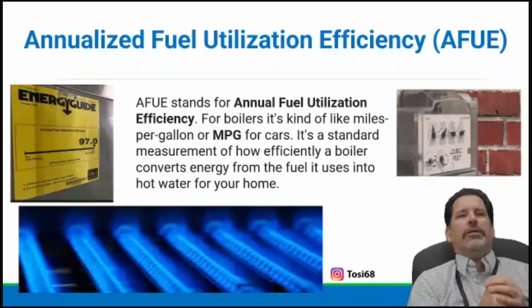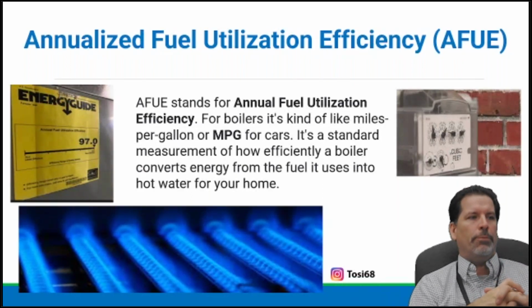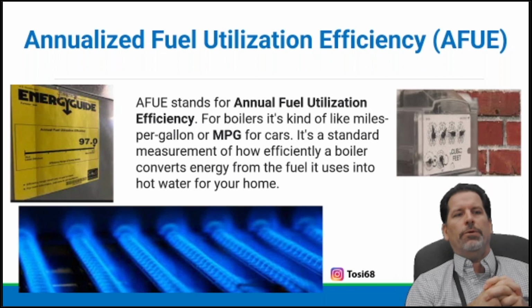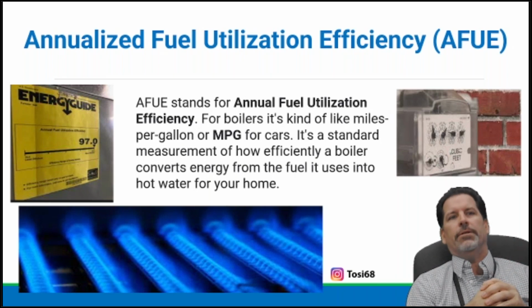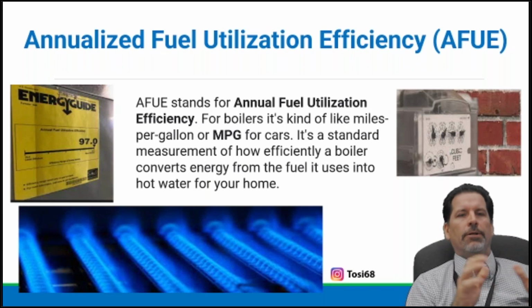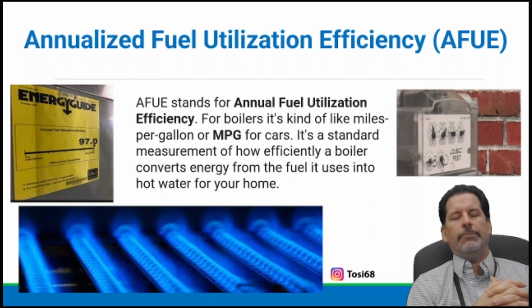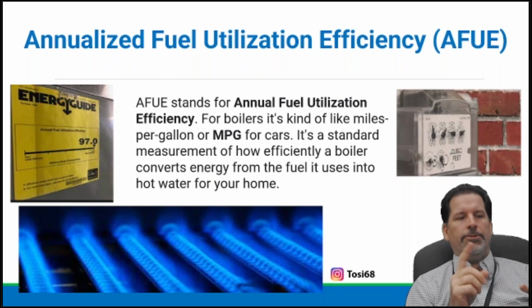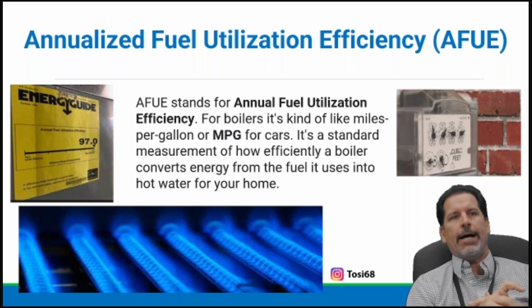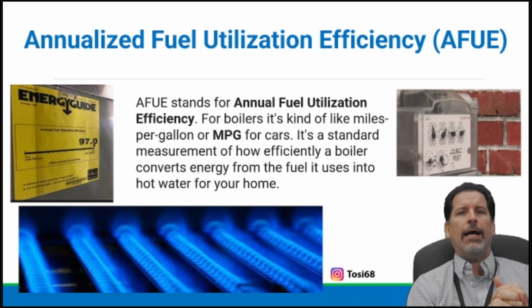So the sticker, let's talk about the sticker. What does the sticker on the side of your boiler represent? Does that mean as soon as you hook it up, you achieve your goal if you have no water on the floor? Like, yay, we did a great thing here. We don't have any leaks. We have all the parts and pieces in all the right spots, but we still don't know what we're delivering, right? Because we're not installing outdoor sensors. We're maxing out our aquastats, or whatever the delivered water temperature is, because we don't know anything different than high temperature, 180, maybe even higher.